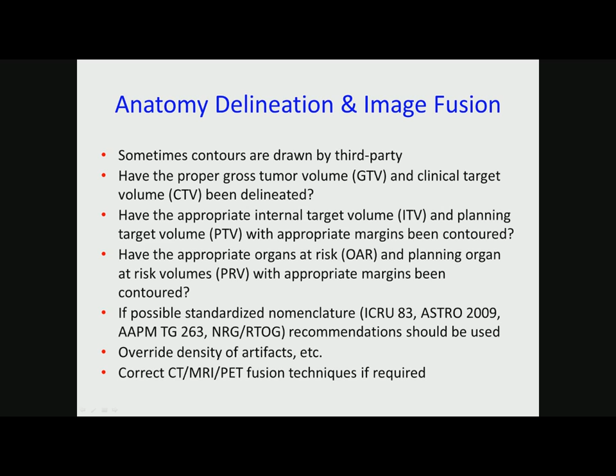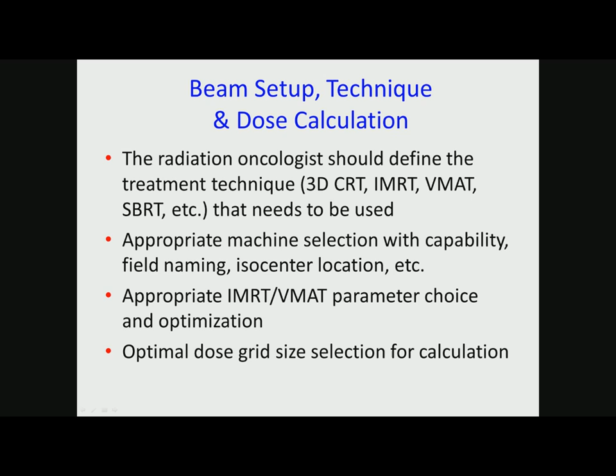As far as dose calculation, I won't say too much about this because this is kind of a black box. Treatment planning system already doing this. If you commission your treatment planning system correctly, this should be working correctly. Except one thing is the dose grid size. You need to make sure that you're consistent, that whoever's doing your treatment plan, if it's a head and neck or a complicated case, you want a 2 mm grid size versus a 3 mm grid size. Sometimes the dosimetrists might want to finish the plan faster because the smaller you make the grid size, the computation time goes up. And so you need to make sure that you have some policies in place to have a fixed grid size for a certain body location, a body site.